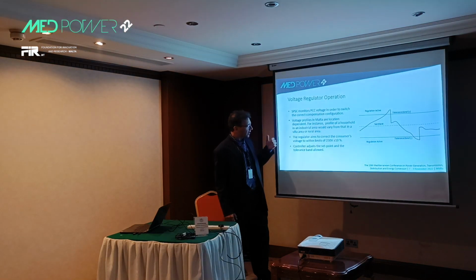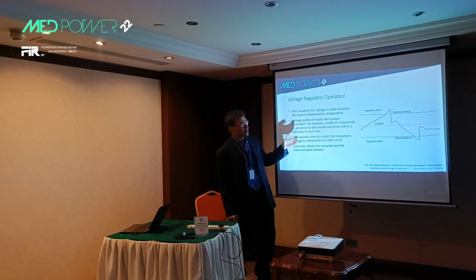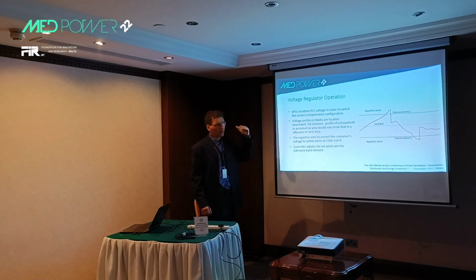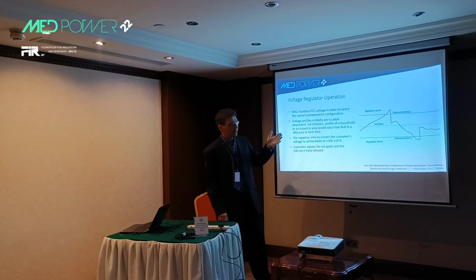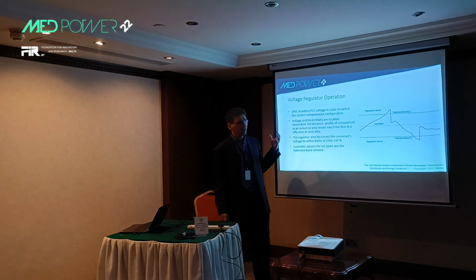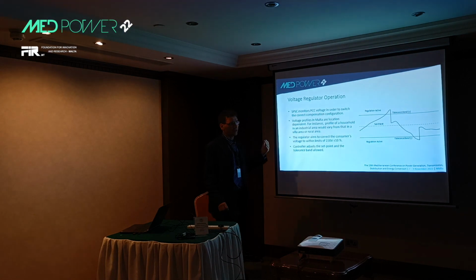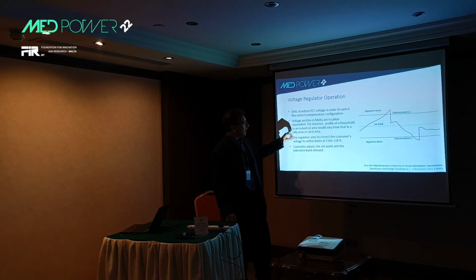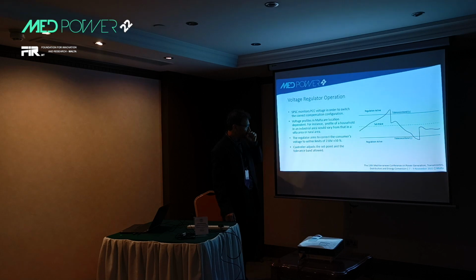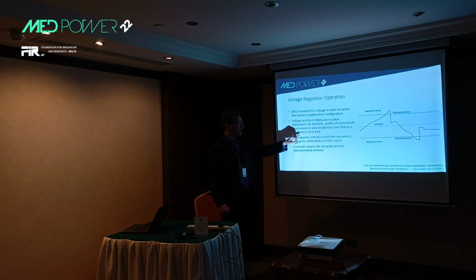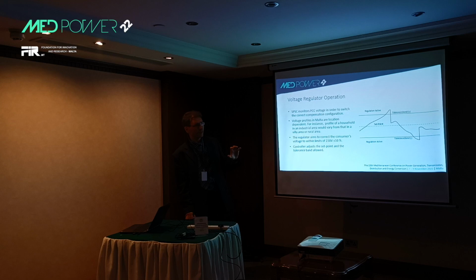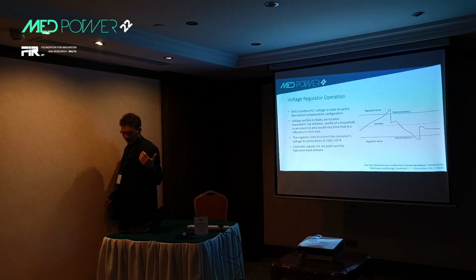Another thing to be said about Malta is that the voltage I showed you, I didn't show you the voltage profile of my house, but basically in my area the voltage profile is quite steady, so it's not one of the best areas probably where to implement this. However, there are a lot of areas where there's a high concentration of PVs, where the voltage profile basically goes up and down quite regularly. So this profile is going to be very location dependent. If you're in an industrial area, it will be different from that in a villa area or in a rural area. Okay? However, the controller that we are designing shall be able to be implemented in whichever area you require, because it can compensate in the positive direction and it can compensate even in the negative direction.